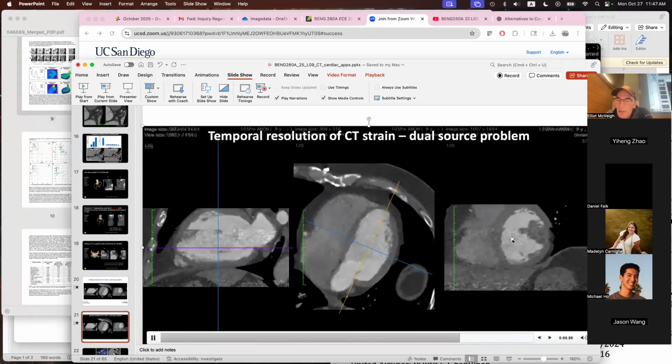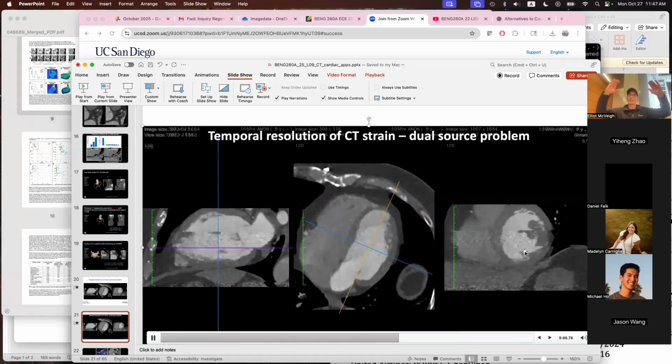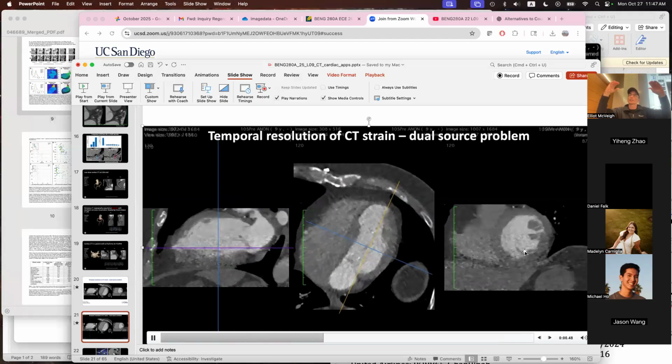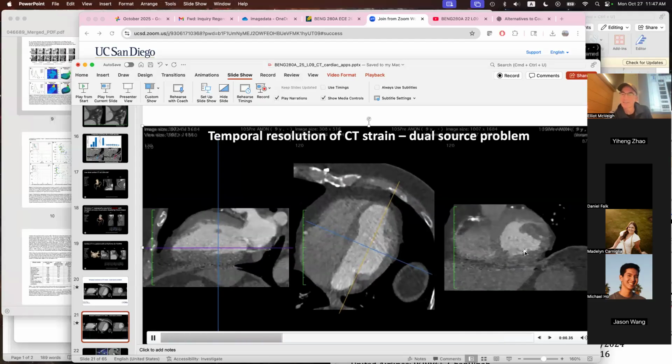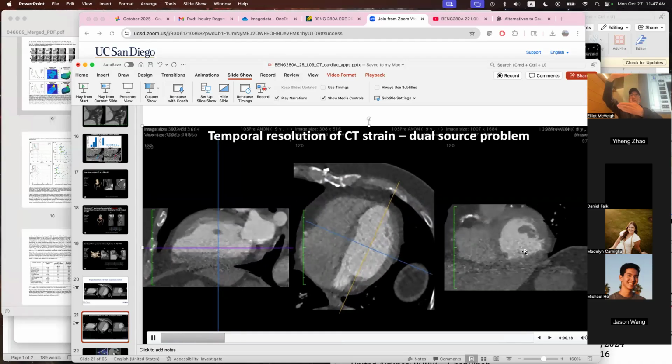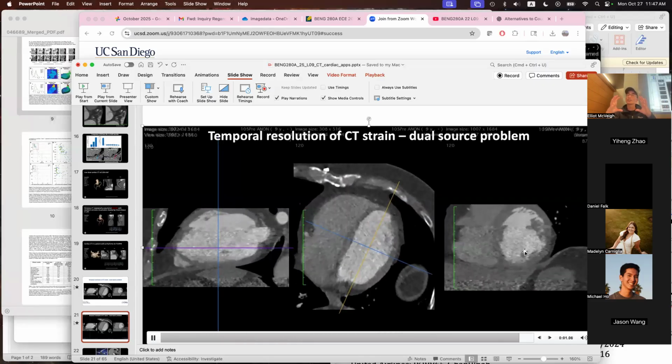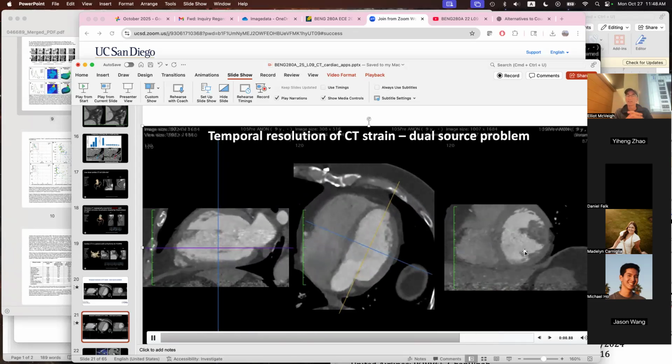Okay, look at this one here. Do you see that coherent 4 centimeter thing floating up through the heart? That's actually a picture of how that detector is rolling through the heart. And on either side of it, that's a beat before and a beat after. And you can see that thing is rolling up. That heartbeat was quite different. The walls are in a different position. The rate at which the thing was beating is different. And so this is called step artifact.